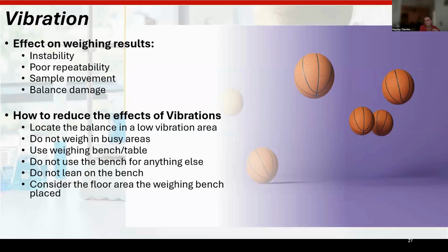The floor the table sits on also does matter, so try to avoid placing it near machinery or high vibration zones, next to a centrifuge that's spinning and vibrating for half of the day. Just be a bit conscious of where you're placing it.